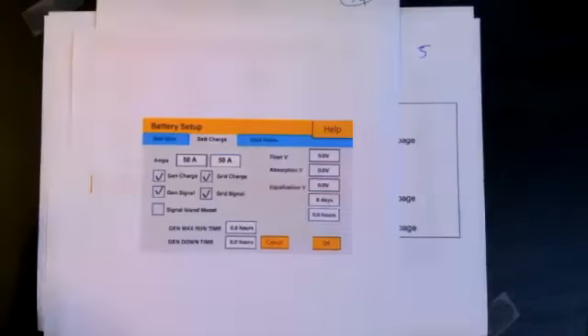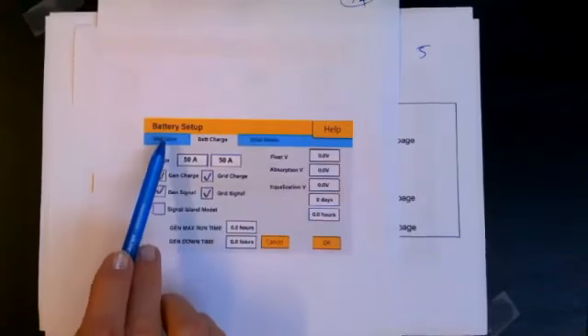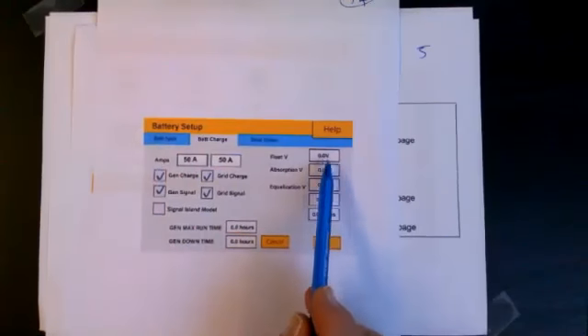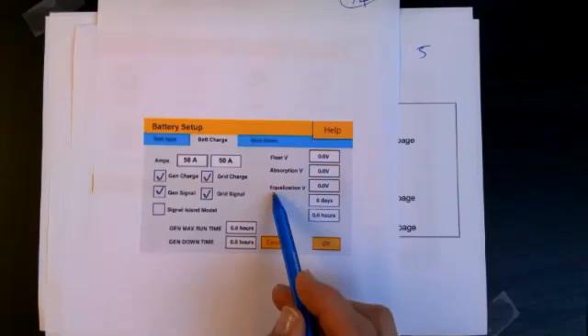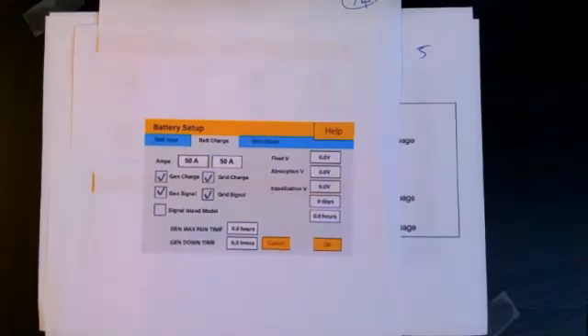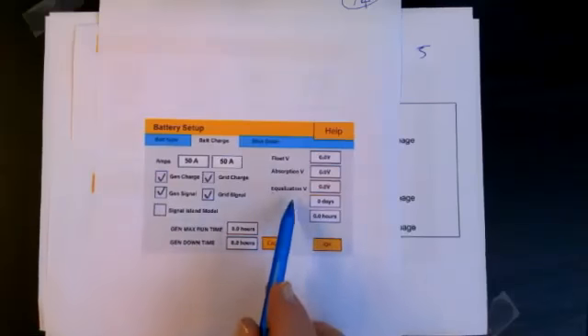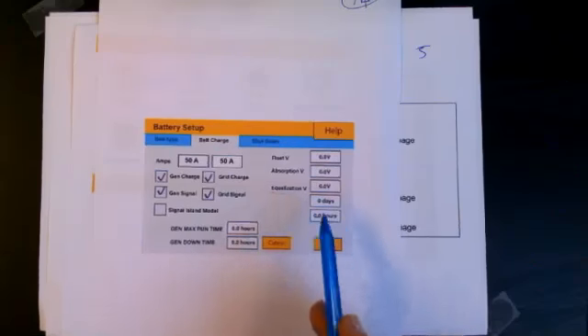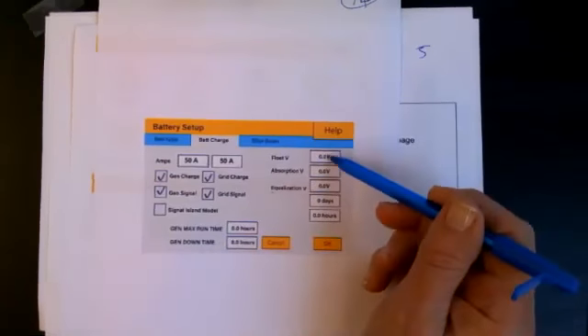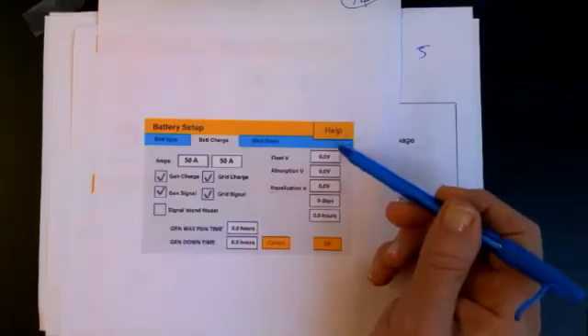Now, I know most people tend to go to lithium batteries because of longevity and lots of benefits, but there are people still using AGM. Also, if you have a lithium battery that's not communicating properly and you've got to go to AGM, then you must set this up as an AGM battery, and you need to know these voltages. If it's a lithium battery, you wouldn't use the equalization. The equalization is for lead acid only. If you use equalization, it puts a higher voltage onto the battery. If it is a lithium battery and you use equalization, you will damage it. Never, ever, ever use equalization on a lithium battery. So these should be set to 0, 0. If you're using a lithium battery without communication, then you have to know these voltages.